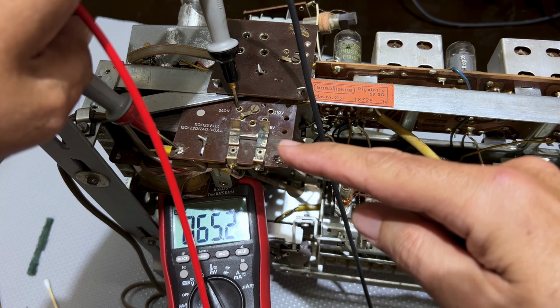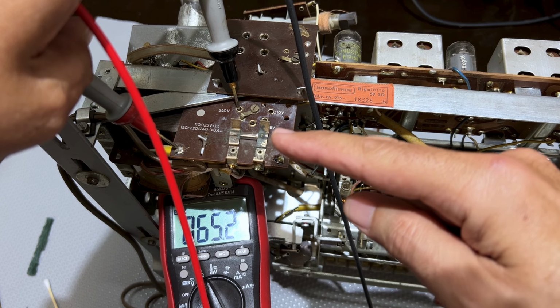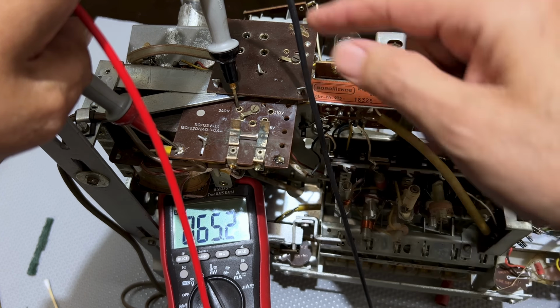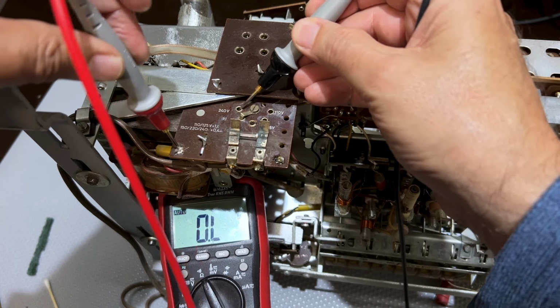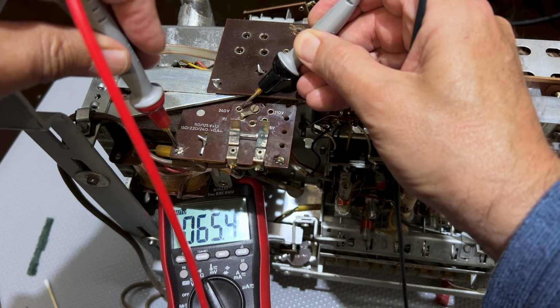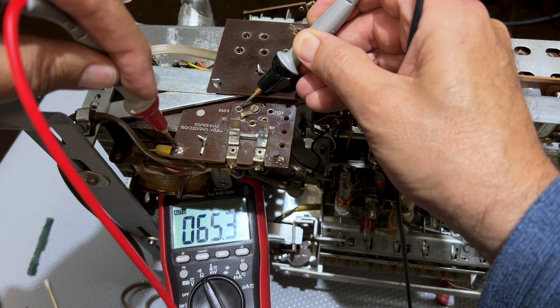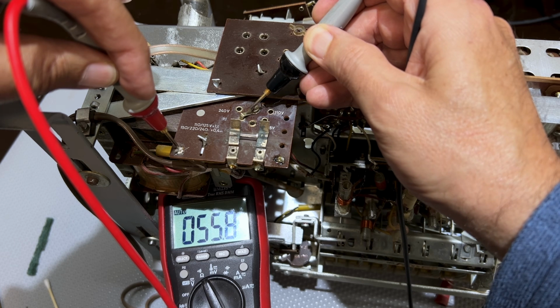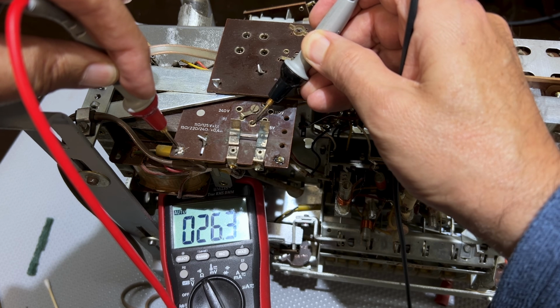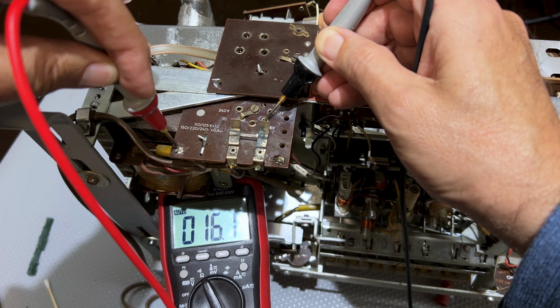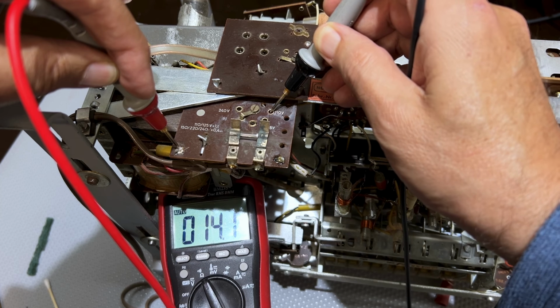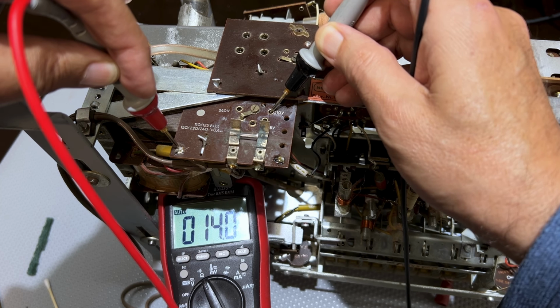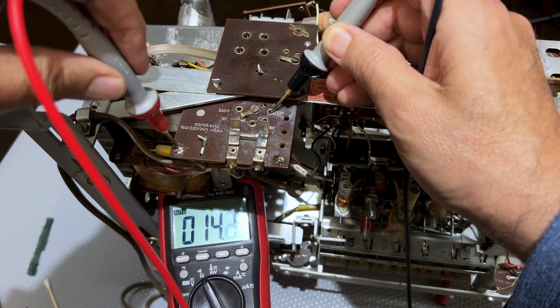According to the schematic, it should be going through the fuse or the switch before it goes to the windings. But what we've got is these are the windings: the 240 volt winding at 65 ohms, the 220 volt winding at 55, 26, 16, and the 110 volt winding at 14 ohms. So it's going straight in there, then it should be coming through to here.